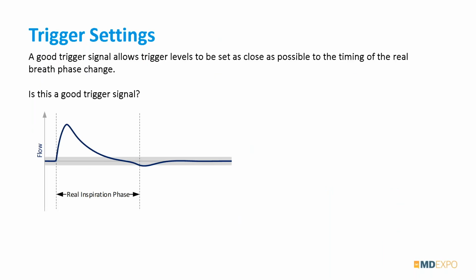So let's say this is our flow waveform that we see on the ventilator or on our gas flow analyzer, and it starts here. This dotted line is the actual real start of the inspiratory phase, and then it rises and falls, and with this dotted line, we know that's when it changes to exhalation. Let's say we want to set trigger settings on this flow waveform. One more thing to mention: when we set our levels, we don't want to go too close to the zero line, because sometimes we have signal noise on our measurements, and we don't want this noise to trigger our analyzer.